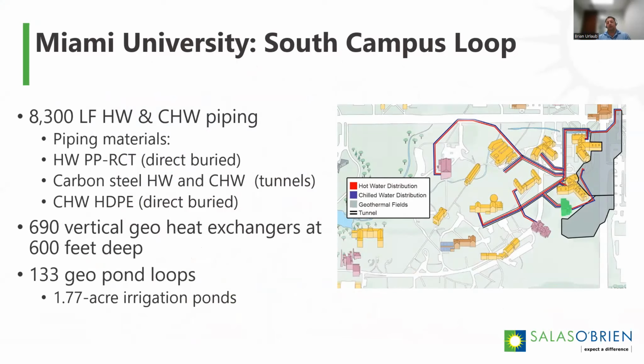That geopond was installed more as a ballast to pre-cool the ground loop in the spring before the summer season, because it was a cooling dominant profile. We wanted to make sure we weren't going to overheat the ground loop. And because they had a man-made body of water for water retention, we put a mat loop in the bottom of that pond, and they circulate that. What they found is they were able to circulate that fluid directly to the buildings for about a month every March and get free cooling without running any chillers, because that pond is still very cold when the ice is coming off, so you're able to get passive cooling. So again, just adding to the efficiency and finding different sources and connecting that to your overall district, you can do some fantastic things to really increase your efficiency.